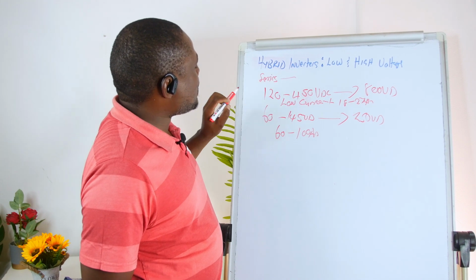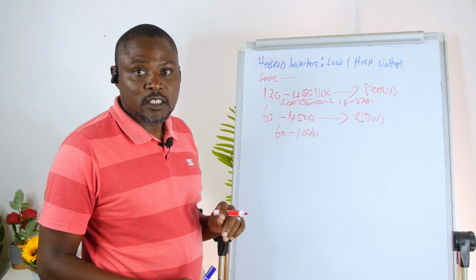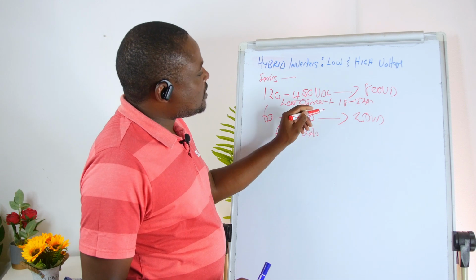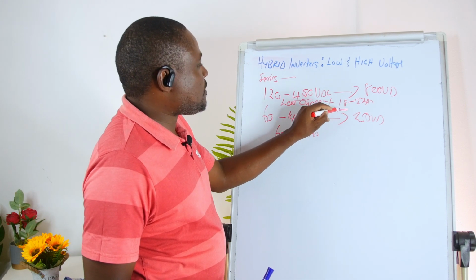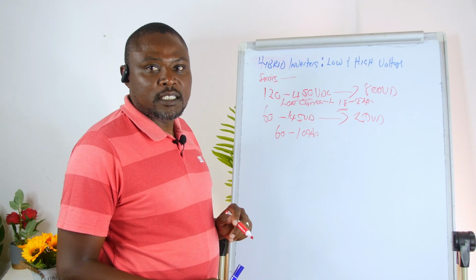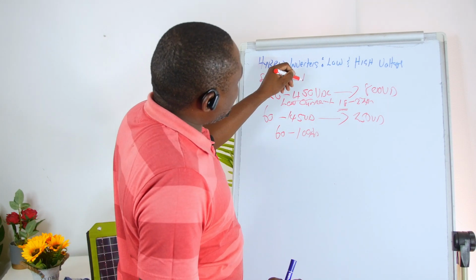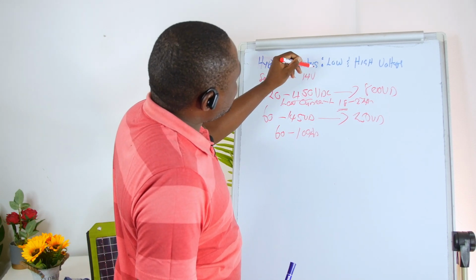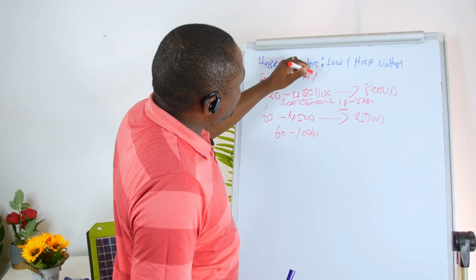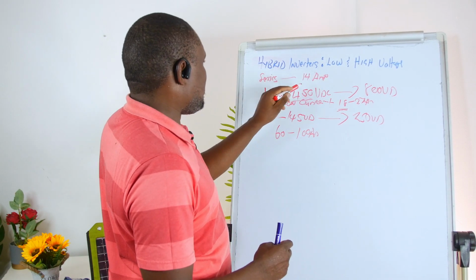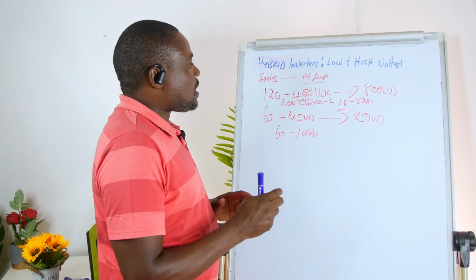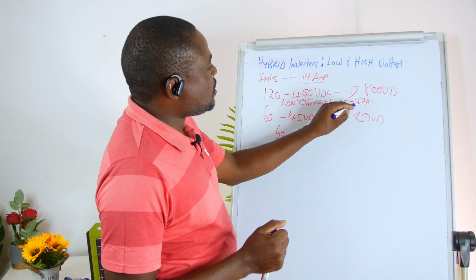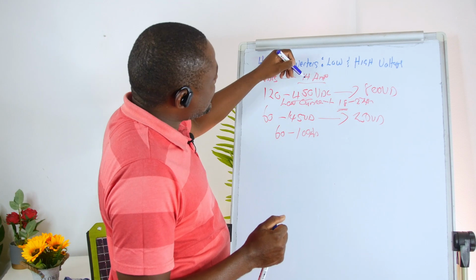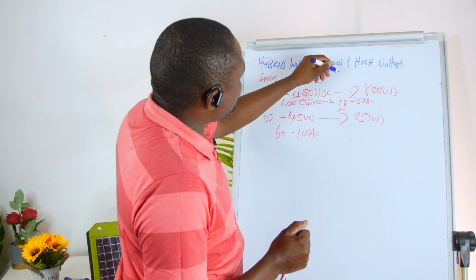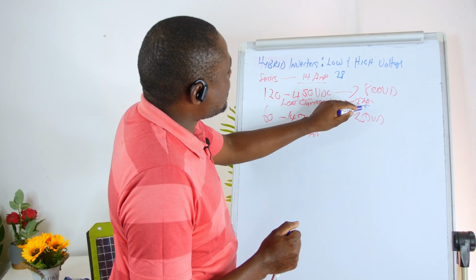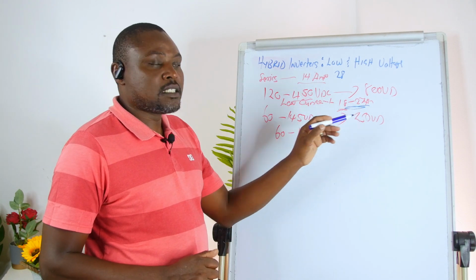All the panels wired to the required voltage. In most cases you can't go parallel-series, especially if you have low current. In this case, most of the panels are rated maybe at 14 amps. So if a panel is 14 amps, if you are going to do parallel-series, it means this current is going to increase, most probably to 28, and our current rating is way lower.